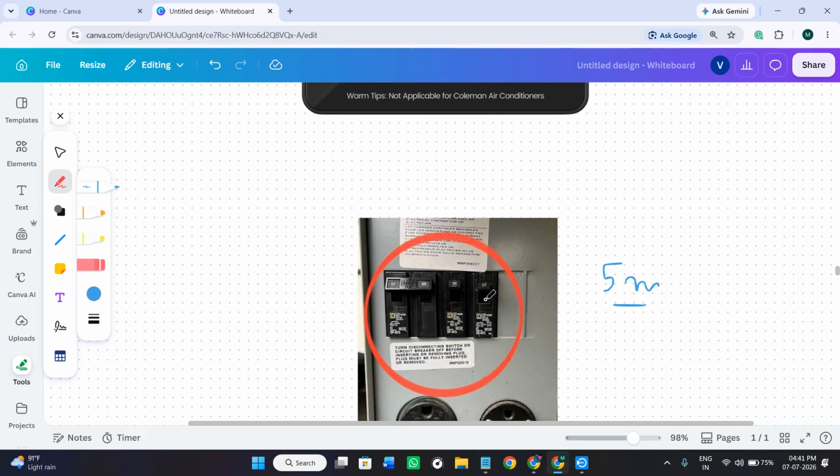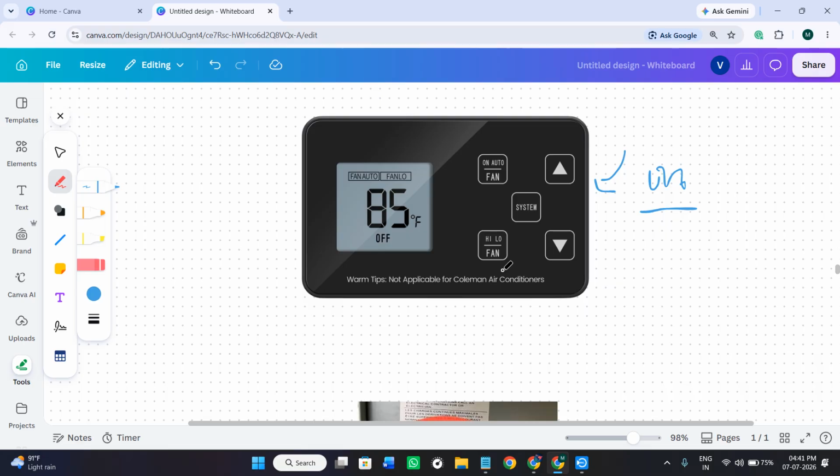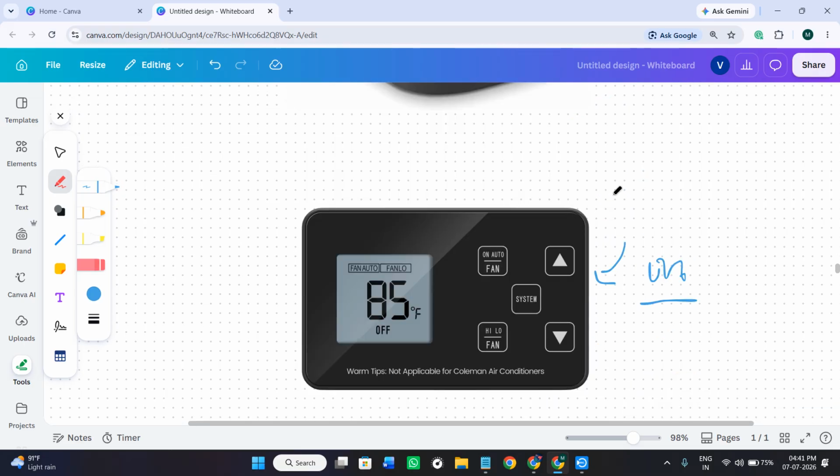Now restore the power in the reverse order. You need to first turn the breaker back on, then reconnect the shore power and start the generator, and then you need to wait for a further 2 to 3 minutes before using your thermostat. During this time the rooftop control board completes its startup sequence.